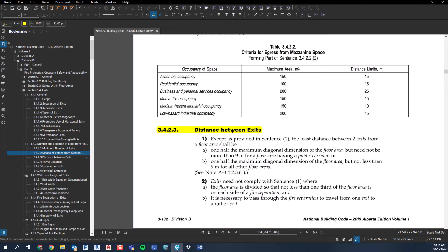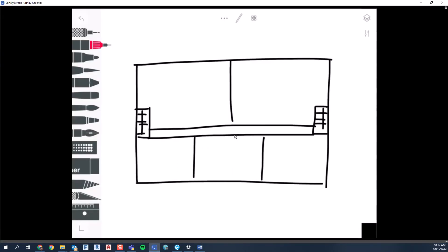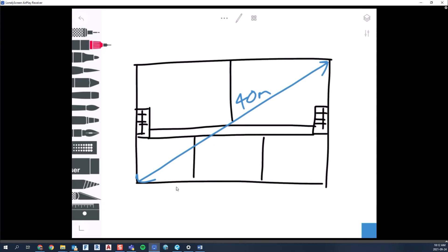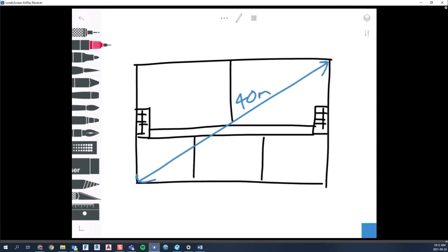Going back to the Building Code, sentence one reads: the least distance between two exits from a floor area shall be one half the maximum diagonal dimension of the floor area, but need not be more than nine meters, for a floor area having a public corridor. I just drew a floor plan with a public corridor, so let's say our diagonal dimension is 40 meters. Half of 40 is 20 meters — that would be the calculated minimum distance between exits.